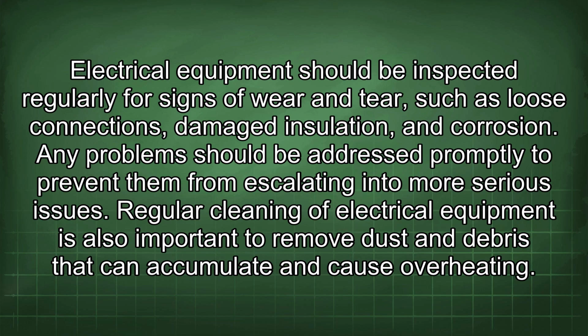Electrical equipment should be inspected regularly for signs of wear and tear, such as loose connections, damaged insulation, and corrosion. Any problems should be addressed promptly to prevent them from escalating into more serious issues. Regular cleaning of electrical equipment is also important to remove dust and debris that can accumulate and cause overheating.